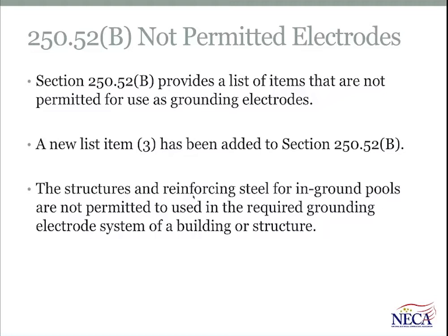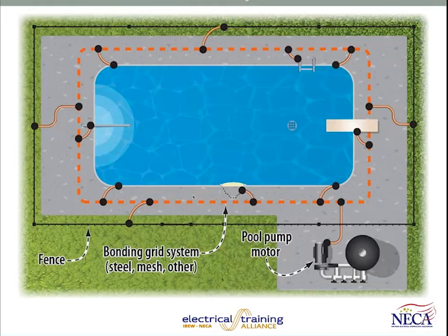There was a proposal to actually recognize that it could be used, and Panel 5 did not react favorably to that. Instead, they basically said that even though it would resemble an electrode and it makes the connection to earth, they didn't want to purposely include it in the grounding electrode system. So we're talking about the in-ground conductive shell that's usually encapsulating rebar that forms the structure of an in-ground pool. All the requirements for creating a common bonding grid and equal potential bonding and so forth are still in play.